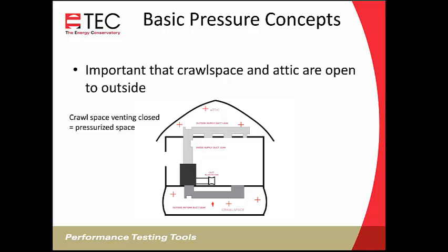But there is certainly an issue in that you're not taking into consideration the leakage around the duct when you're doing that. So you're not necessarily getting an accurate measurement. We don't go into a lot of detail in our manual with that issue. We do talk about, if you're using duct mask register sealing tape and you tape onto the wall, you might have problems peeling paint off or something on that order. So we recommend not taping to the wall for that reason. But you want to be consistent in how you're doing it, consistent across your company, and, if you're a HERS rater, consistent with what your HERS provider recommends on that topic.